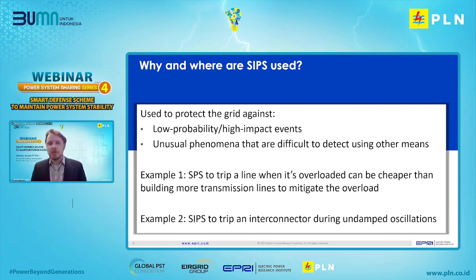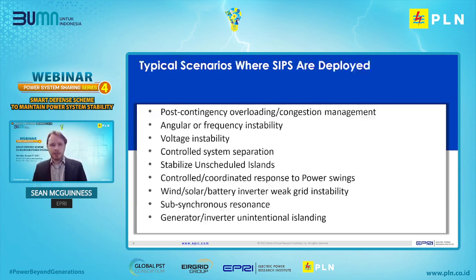The second major case where it's deployed is unusual phenomena that are difficult to detect using other means. So this may be cases of undamped oscillations between areas, controlled system separation, controlled load shedding, and things of that nature. So these are defending the system against these unusual phenomena that really can't be tackled in other ways.